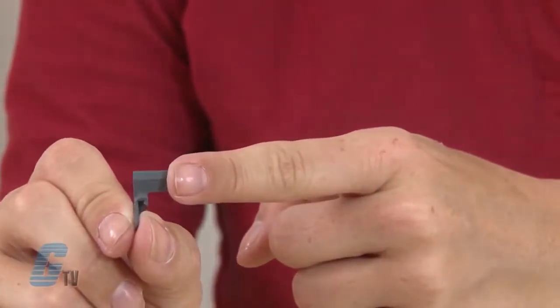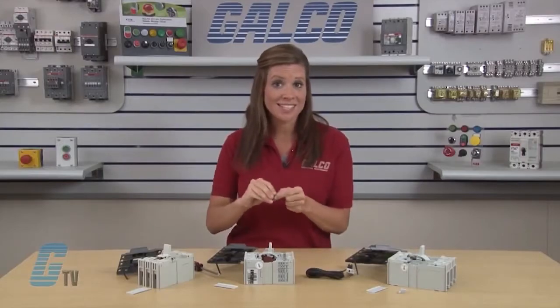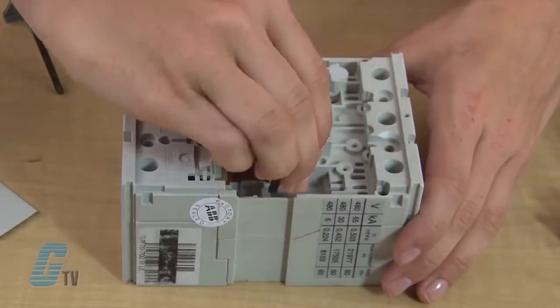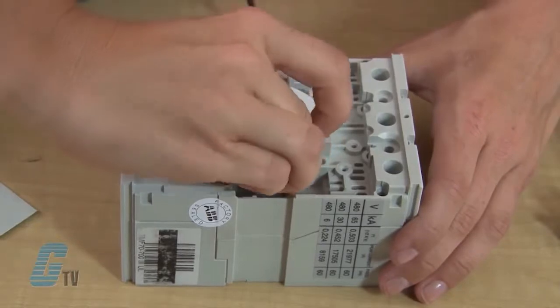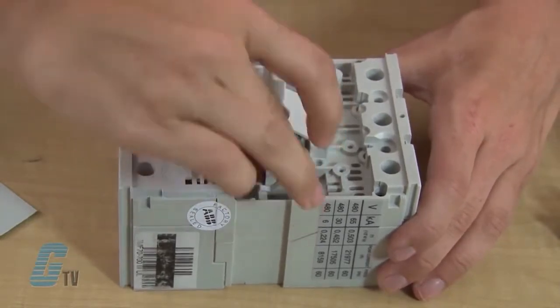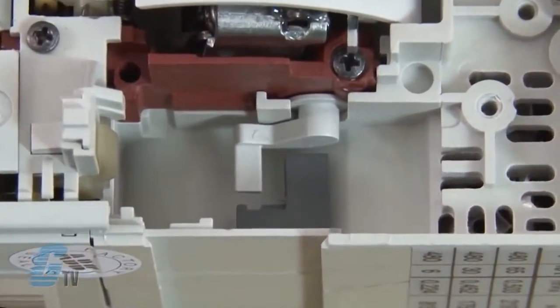For the T2 circuit breaker, I'll select the gray adapter, which is also marked with T2 molded in the plastic. I'll insert the tapered tab into the slot at the back of the accessory port on the right side of the breaker. The adapter is seated properly when it drops all the way down freely into the slot.